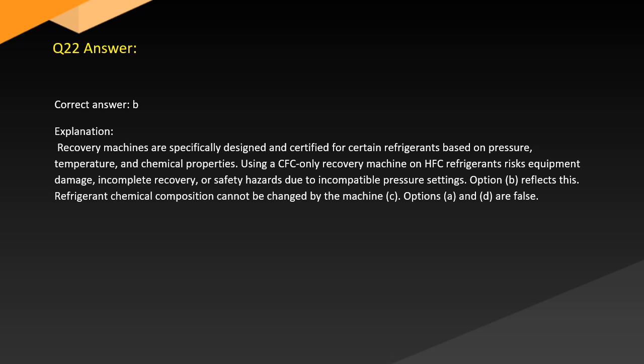Answer. Correct answer: B. Explanation. Recovery machines are specifically designed and certified for certain refrigerants based on pressure, temperature, and chemical properties. Using a CFC recovery machine on HFC refrigerants risks equipment damage, incomplete recovery, or safety hazards due to incompatible pressure settings. Option B reflects this. Refrigerant chemical composition cannot be changed by the machine, so C is false. Options A and D are false.